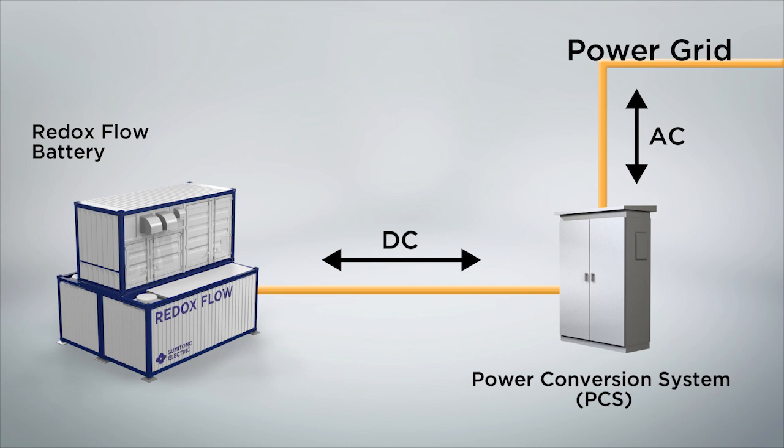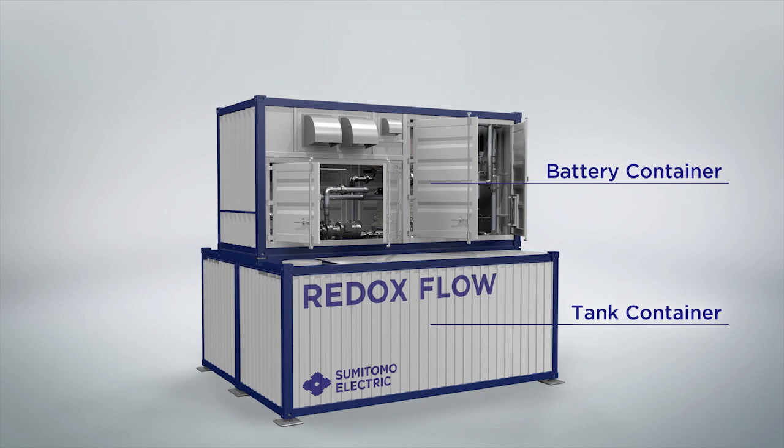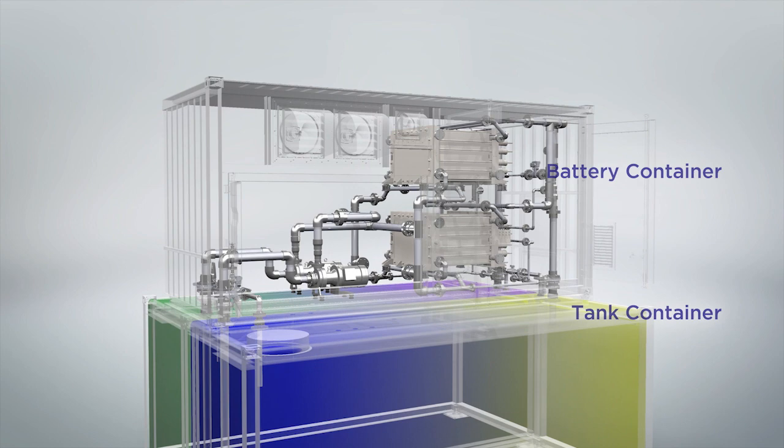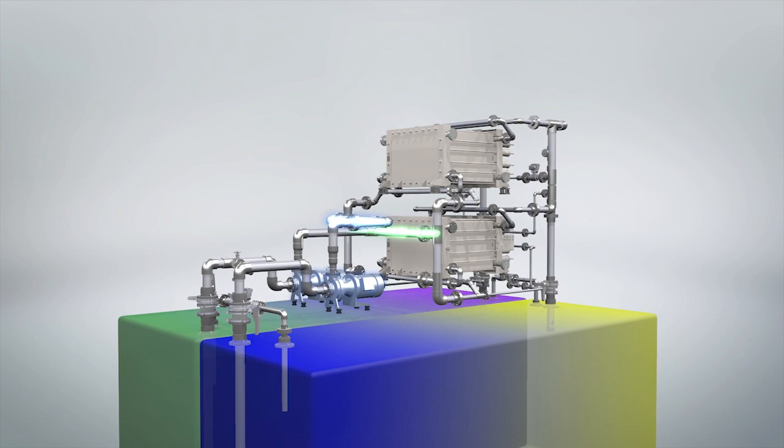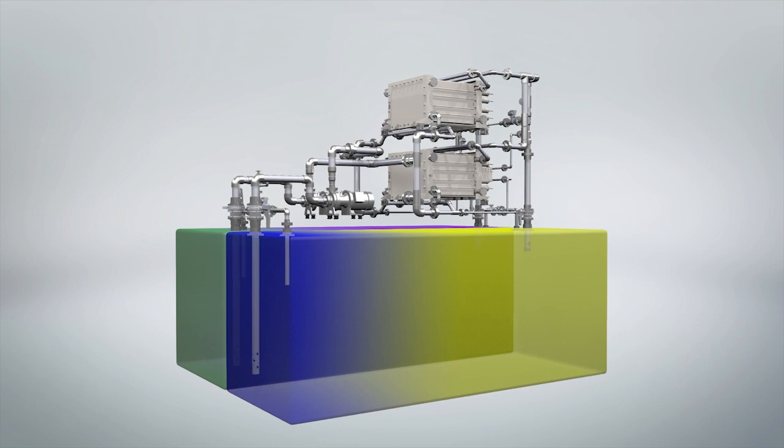The redox flow battery has a two-tiered structure with two containers. The top half is the battery container that holds the cell stacks, pumps, and controllers. The bottom half is the tank container that stores the positive and negative electrolytes. A pump circulates the electrolyte during charge and discharge, sending it from the tank to the cell stack and back to the tank after the charge-discharge reaction takes place.